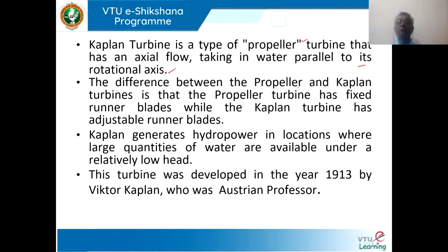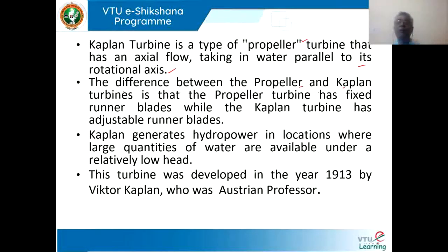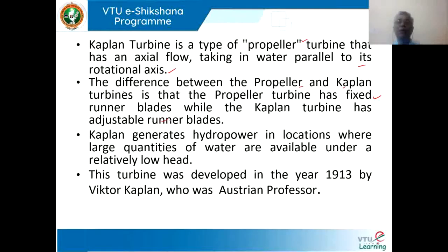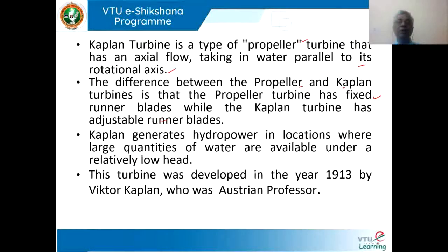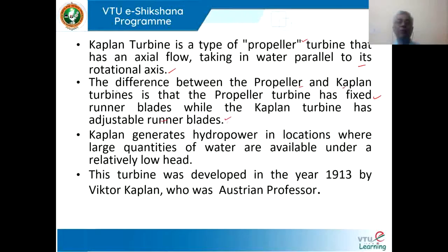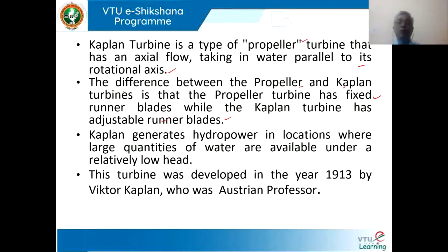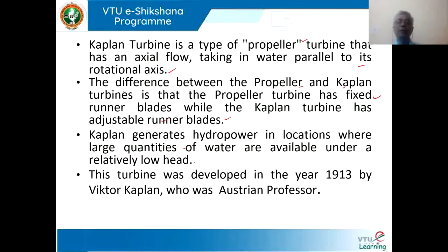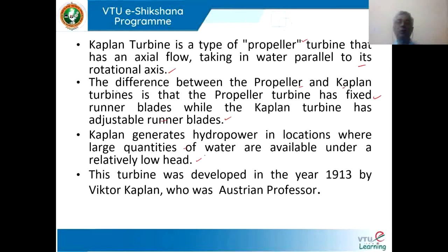The difference between a propeller turbine and a Kaplan turbine: propeller turbine will have fixed runner blades, whereas the Kaplan turbine has adjustable blades. That is the only difference between the Kaplan turbine and the propeller turbine. Kaplan turbine is used in hydro-power projects where large quantities of water are available and the available head is very low.